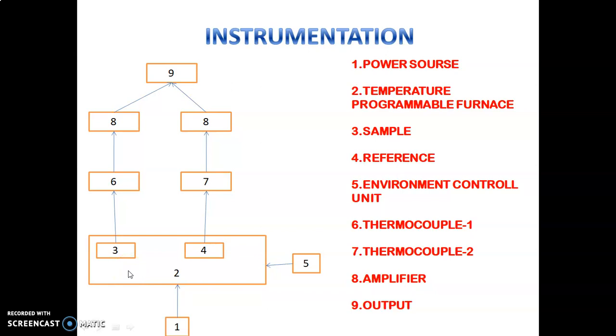When changes take place, a difference in temperature can be seen. If the sample undergoes a reaction like sublimation, it is an endothermic reaction, which means during that reaction it absorbs more heat from the system. So the temperature of the sample will be lower compared to the temperature of the reference material. If it undergoes an exothermic reaction, some heat is donated outward, which means the sample experiences a higher temperature than the reference material. This is one of the key advantages of differential thermal analysis: we can analyze whether a reaction is exothermic or endothermic.